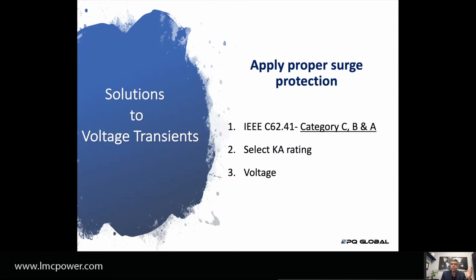It makes sense that category C is a larger unit because it protects against anything coming from outside, from a substation, lightning, everything we just discussed. Category B is designed to protect against elevators, air conditioners, motors, or anything that can start and stop inside a building, still a good-sized transient, but not as big as one from outside. Category A is designed to protect assuming you've done a good job with C and B, since it's a lesser level of protection. You also have additional protection inside rectifiers and UPSs, but you want to keep the transient outside that chassis so the electronics of the expensive equipment don't get affected.